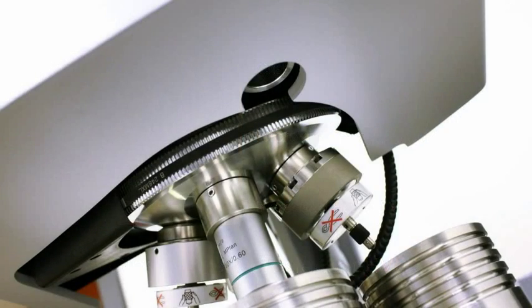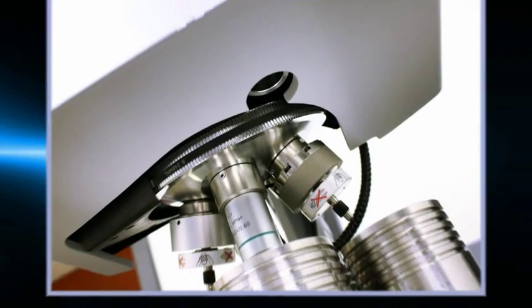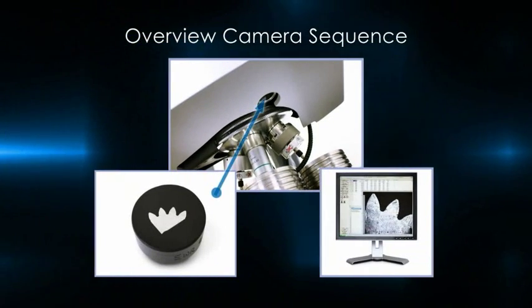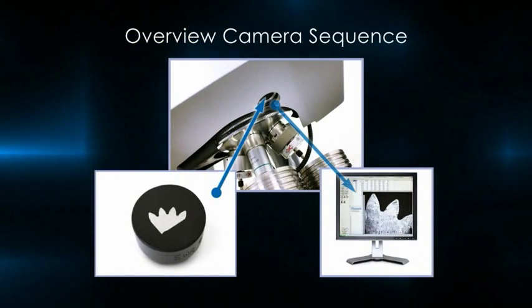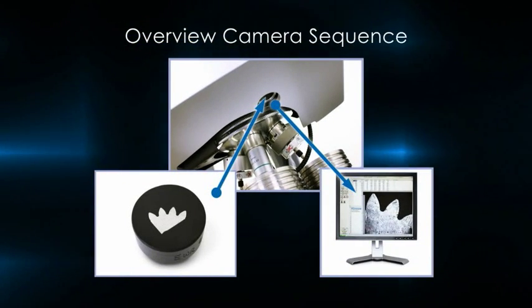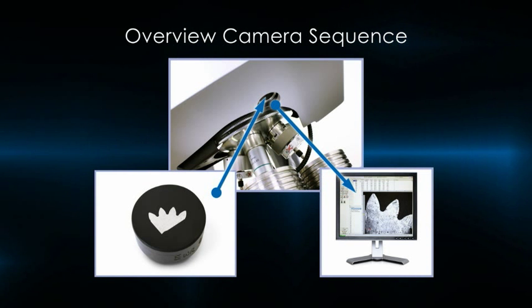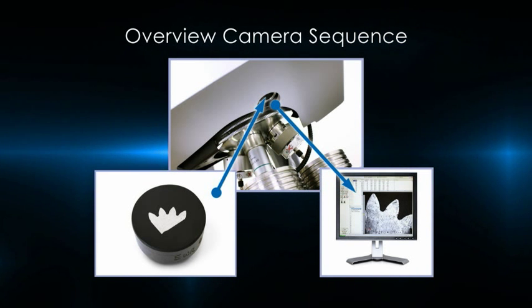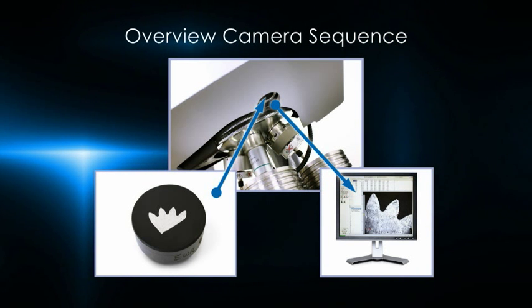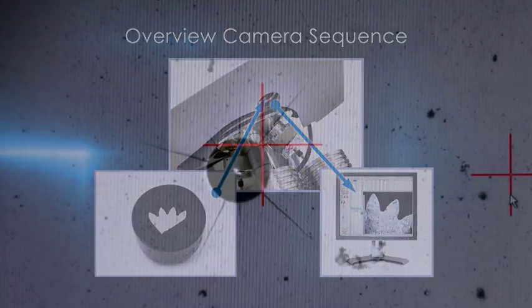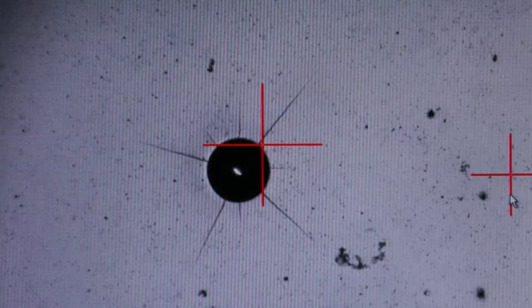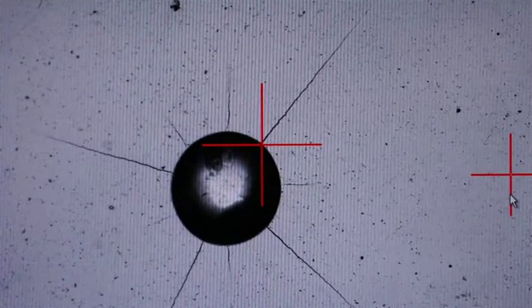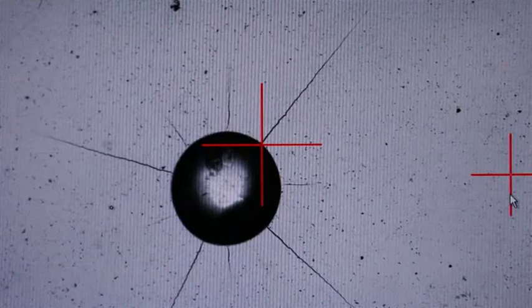The overview camera provides a wide field of view, allowing the operator to see the entire specimen image, and therefore quickly and easily locate and set up traverses for testing. New calibrated digital zooming offers the widest magnification range available on any hardness tester. Magnifications can range from 30 to 2,000 times while maintaining high-quality imaging.